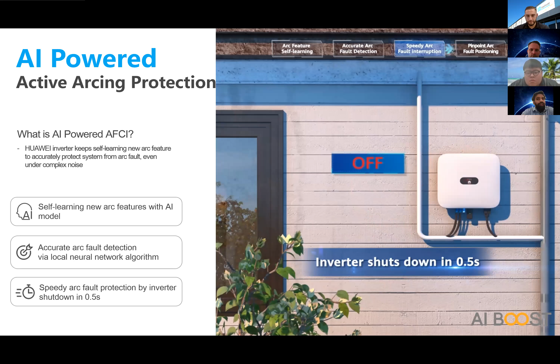And if you have a full optimized system, it will show you where the arc is. So that's the other benefit of having a full optimized system. It will show you where the arc is. Otherwise, it will just show that string 1 has a DC arc fault.